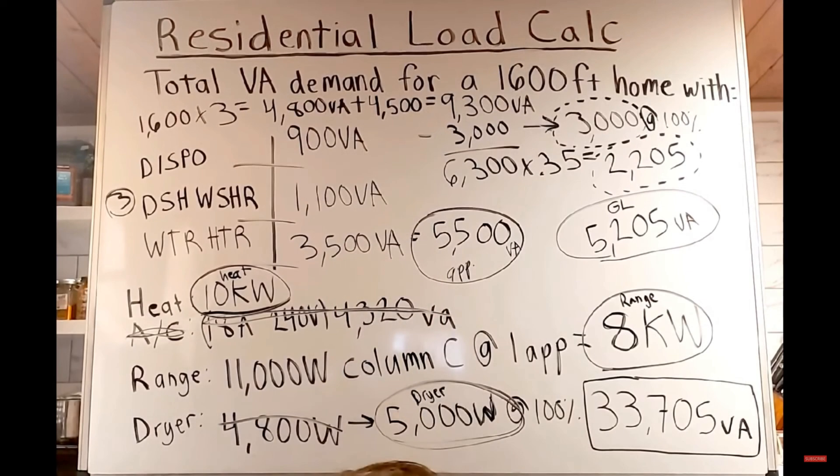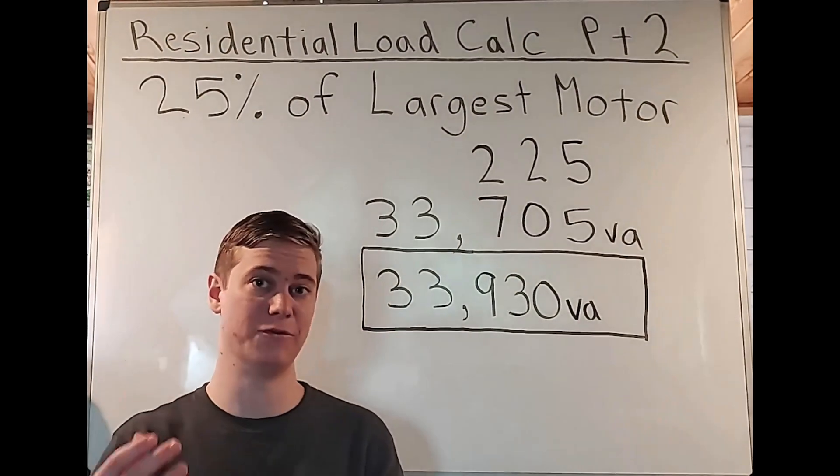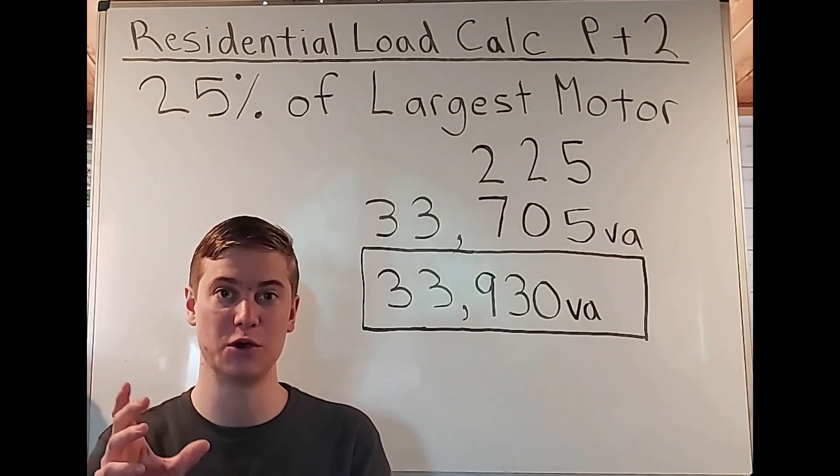So we're going to be taking the 900 volt amps from the disposal. And we're just going to multiply that by 25%, which is 0.25. And we're going to get 225 volt amps. And now if we look back at the screenshot, since our final answer for everything that we did in that video was 33,705, we get 33,930 volt amps. Now this is the answer for the total demanded load for that dwelling.